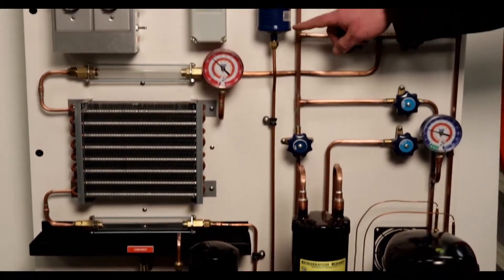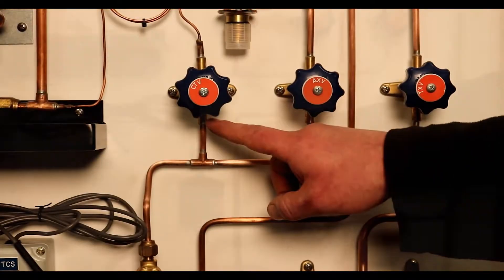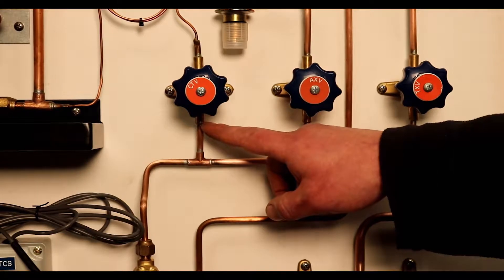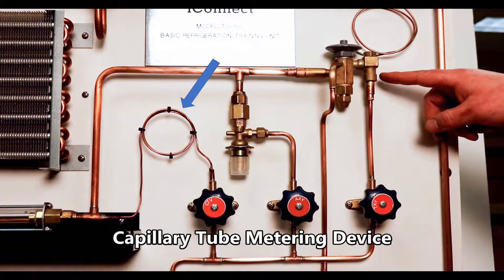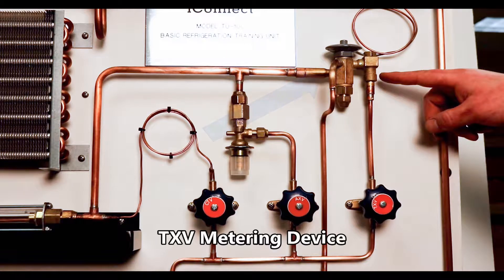The liquid line is equipped with a filter dryer and a moisture-indicating sight glass. The TU-100 can be operated with one of three metering devices: a capillary tube, an AXV (automatic expansion valve), and a TXV (thermostatic expansion valve).